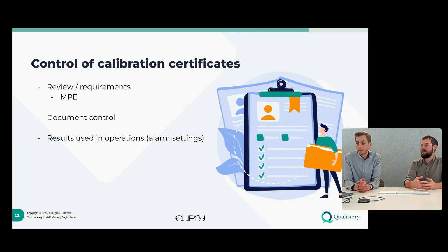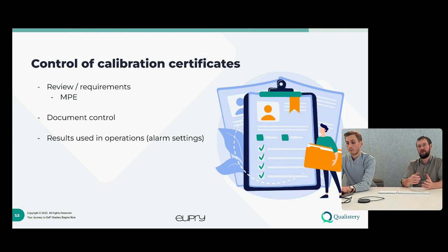I think some of the more frequently missing reviews are often related to: have you actually investigated the certificate, and does it have the results that you expected it to have? So was your MPE below what you expected the MPE to be below? And is the certificate actually the certificate for the specific unit you have in your hand when you're doing the review? Those are fairly simple reviews to perform, but often we're seeing them not being performed and not being documented.